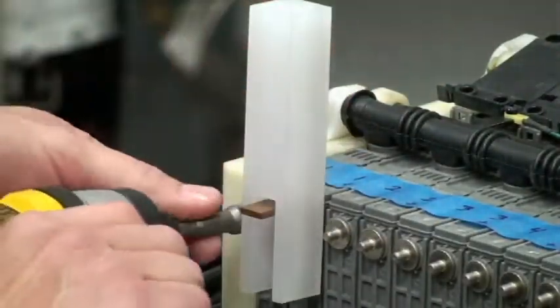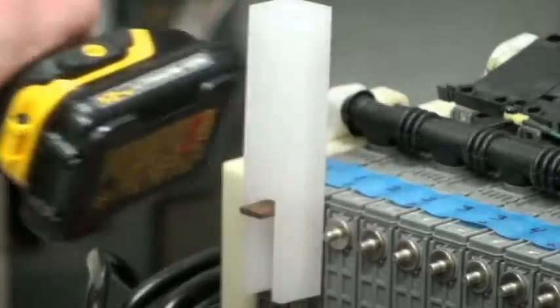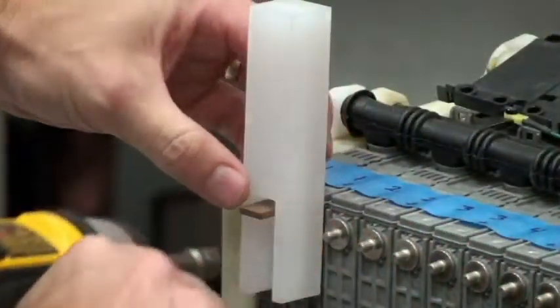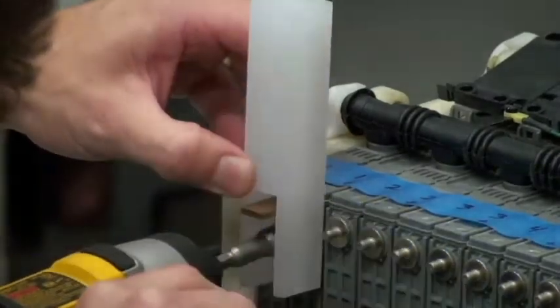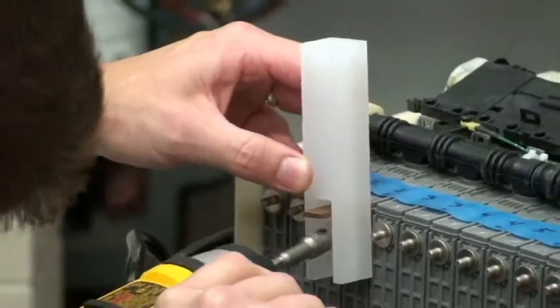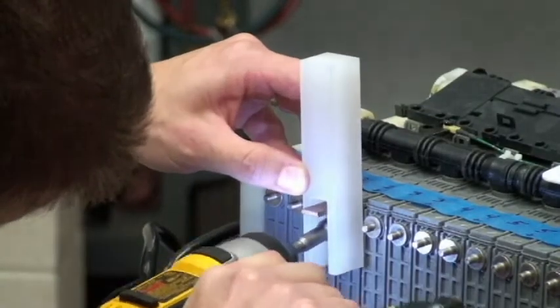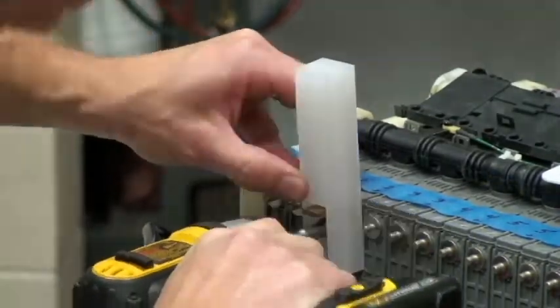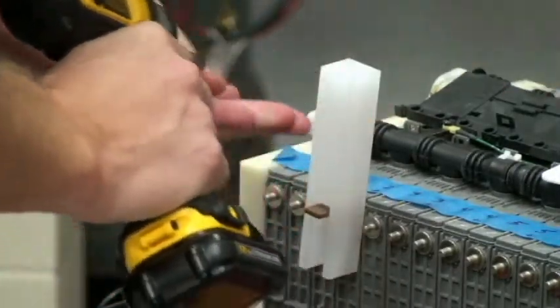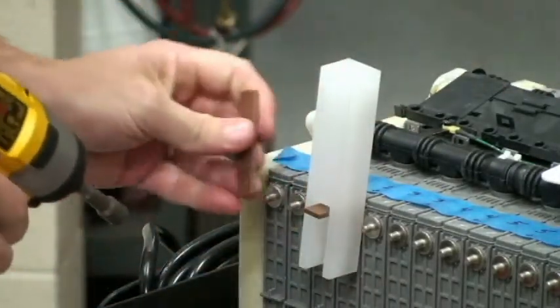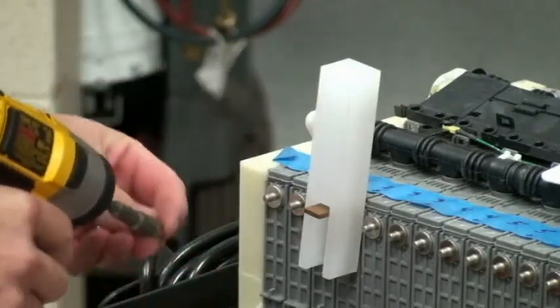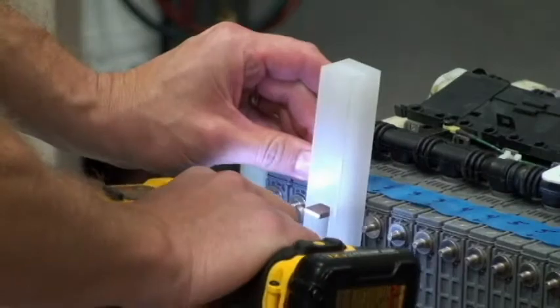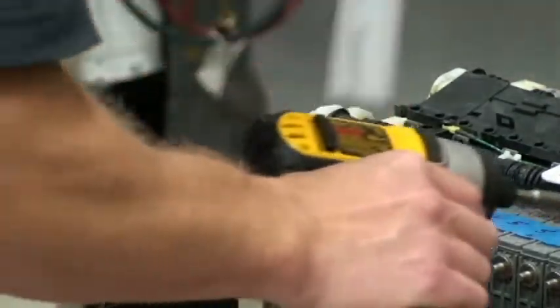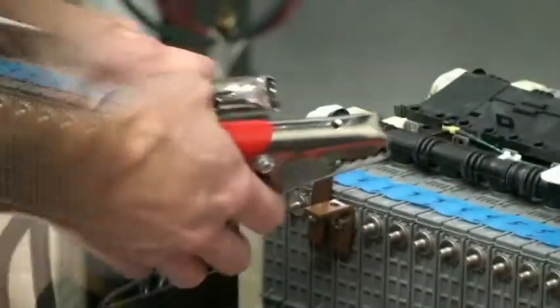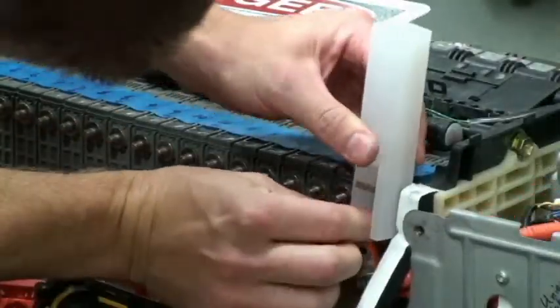Once the first test is completed, the bus bars are then moved to the next pair of battery modules, and again, the isolator bar and bus bars are used to do this. The use of the isolator bar ensures that there is no arcing between the bus bars when installing and removing the bus bars. Once again, once the bus bars are installed, the clamps are installed for the test.